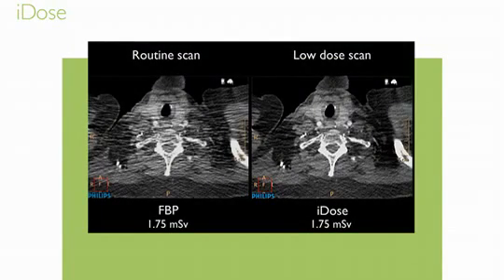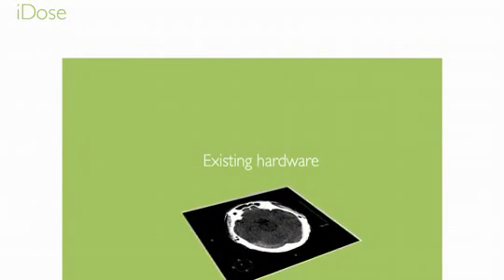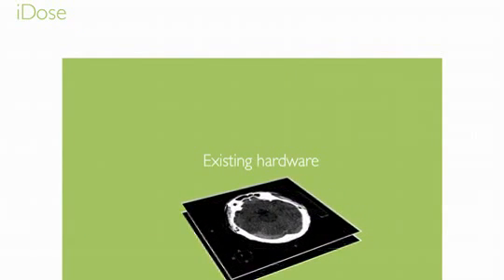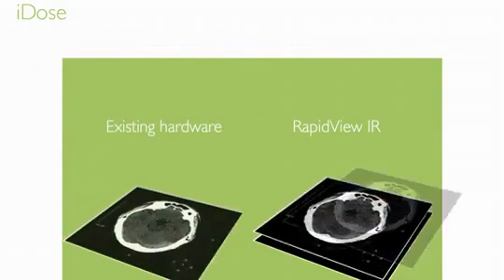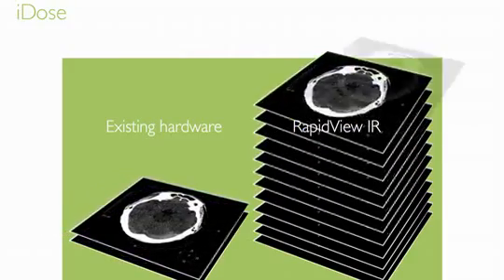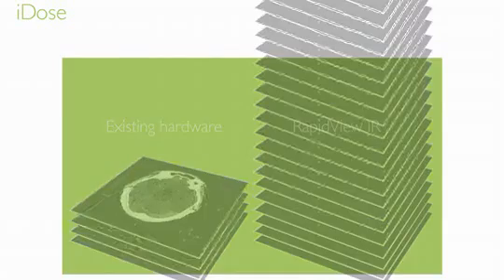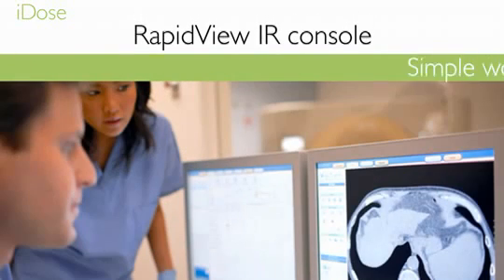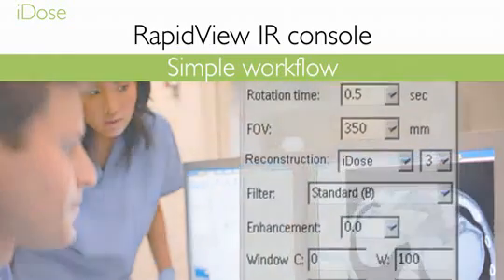iDose's groundbreaking algorithm delivers these outstanding results. But this algorithm is so computationally intensive that it could not run on existing reconstruction hardware. To satisfy the performance requirements of iDose, the RapidView IR console was developed. The computational intensity of RapidView IR enables reconstruction times up to 20 images per second, making it practical to use in the real world. Yet the simple workflow makes it easy to incorporate into your existing standard of care.